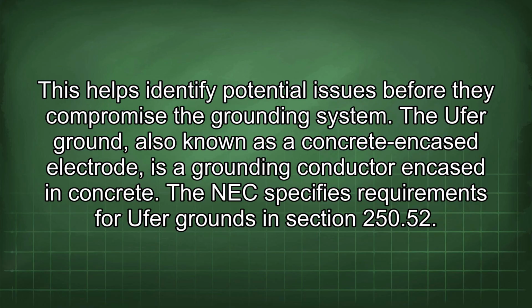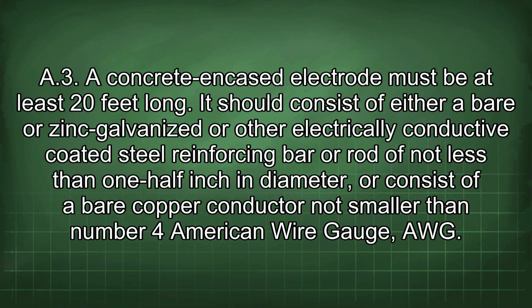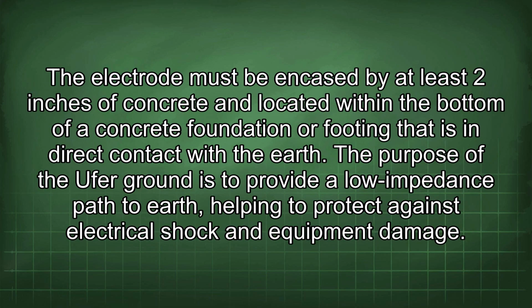The Ufer ground, also known as a concrete encased electrode, is a grounding conductor encased in concrete. The NEC specifies requirements for Ufer grounds in section 250.52(A)(3). A concrete encased electrode must be at least 20 feet long. It should consist of either bare or zinc galvanized or other electrically conductive coated steel reinforcing bar or rod of not less than 1/2 inch in diameter, or consist of a bare copper conductor not smaller than number 4 American Wire Gauge (AWG). The electrode must be encased by at least 2 inches of concrete and located within the bottom of a concrete foundation or footing that is in direct contact with the earth.